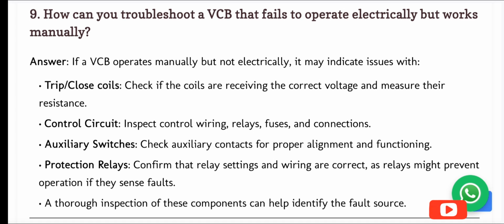Answer. If a VCB operates manually but not electrically, it may indicate issues with trip close coils. Check if the coils are receiving the correct voltage and measure their resistance. Control circuit. Inspect control wiring, relays, fuses, and connections. Auxiliary switches. Check auxiliary contacts for proper alignment and functioning. Protection relays.